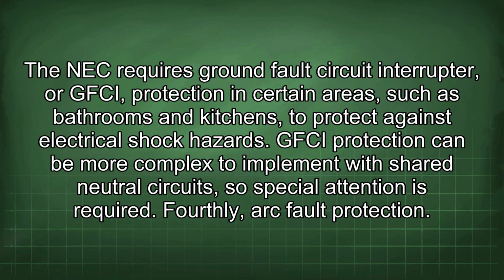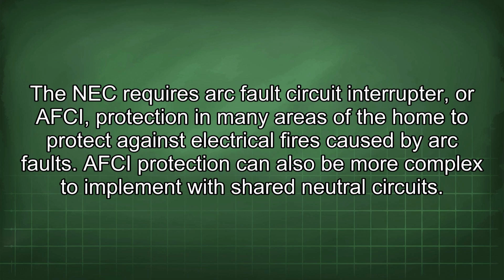Thirdly, ground fault protection. The NEC requires ground fault circuit interrupter, or GFCI, protection in certain areas such as bathrooms and kitchens to protect against electrical shock hazards. GFCI protection can be more complex to implement with shared neutral circuits, so special attention is required. Fourthly, arc fault protection. The NEC requires arc fault circuit interrupter, or AFCI, protection in many areas of the home to protect against electrical fires caused by arc faults. AFCI protection can also be more complex to implement with shared neutral circuits.